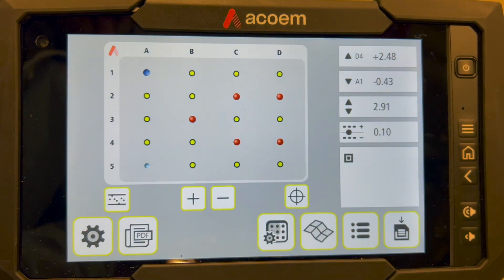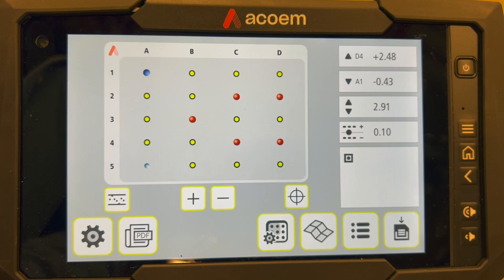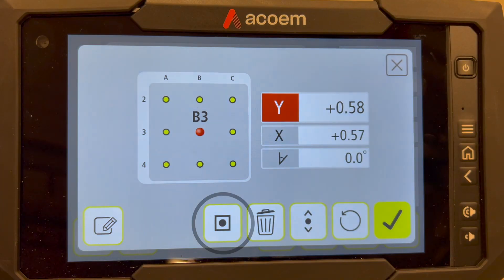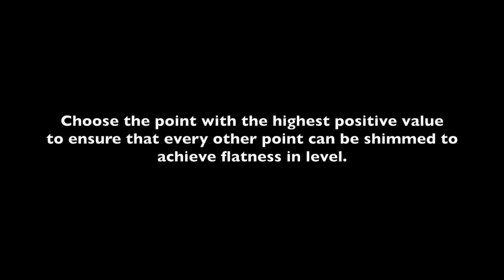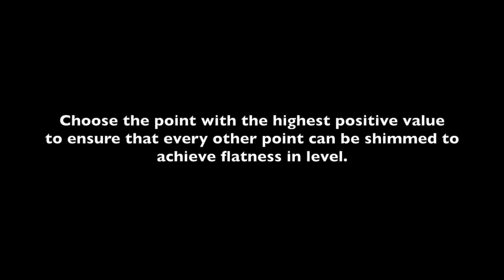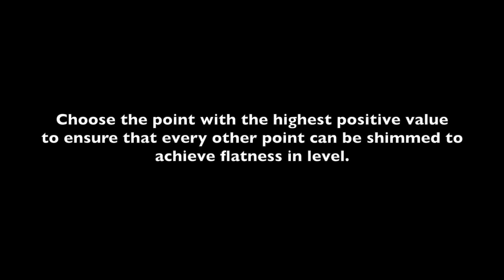Record the values, the same procedure as earlier. Choose one reference point. Choose the point with the highest positive value to ensure that every other point can be shimmed to achieve flatness in level.